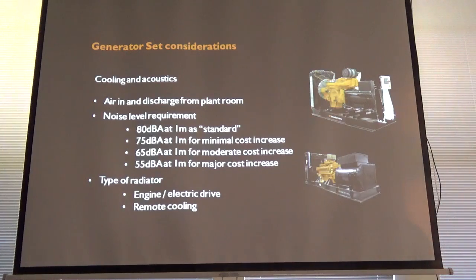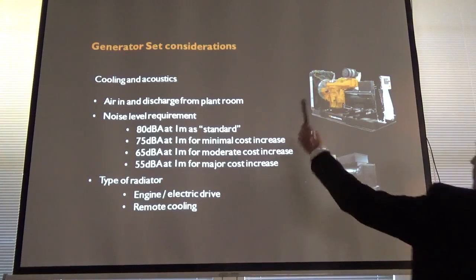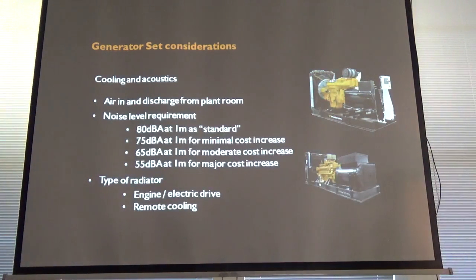I like things as simple as possible. Types of radiator: you'll notice on that one, I like a set-mounted radiator and I'll use it wherever possible. With these sort of designs, for drawing the air in, you've got a 250 Pascal limit. Often we get questions, with consultants saying it needs to be remote cooled. Well, okay. How much less airflow do you think you need to pull through that engine compartment if you took away that radiator and put in a plate heat exchanger and then banged a roof-mounted radiator up top?